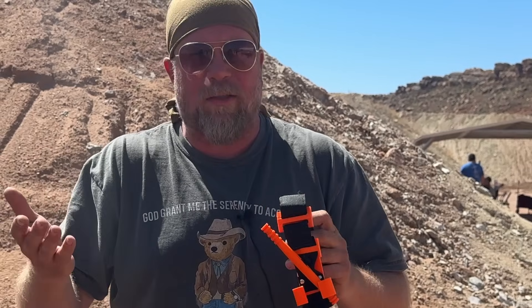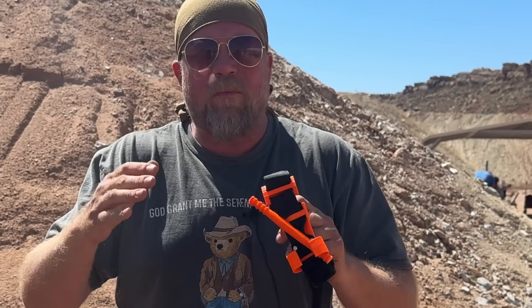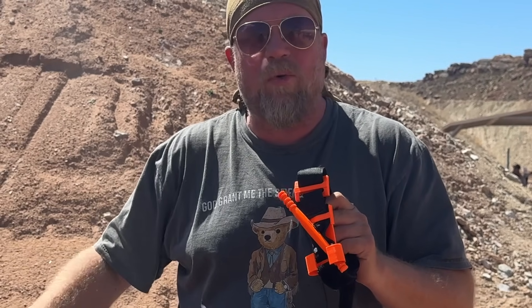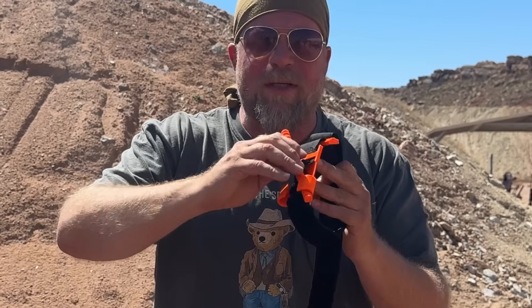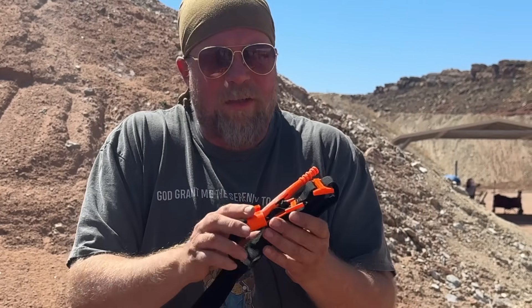If you want to learn more about this, you can find it at glia.org — I'll put a link in the description below. It's interesting to note that data collection about tourniquets under stress isn't something you see happening a lot in the field. You'll see it in sanitary environments, but not on someone screaming with a wound. Here they have time stress — shooters running through on the clock — and the group is collecting data on how many turns of the windlass it takes to cause occlusion and whether the person actually achieved occlusion. They're giving that data back to manufacturers and designers to hopefully improve the product and save more lives. I'm thankful for them doing that out here. If you want to see more, glia.org. Thanks for watching, stay tuned for more.